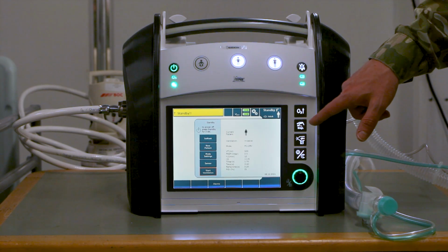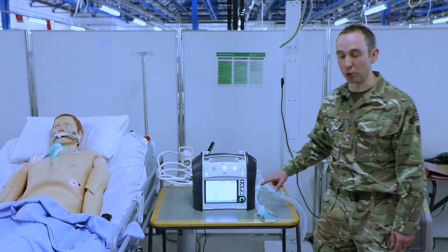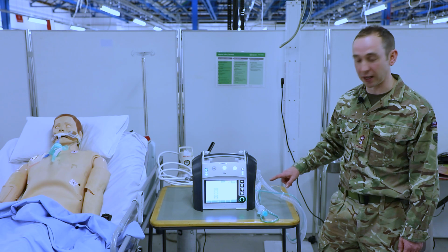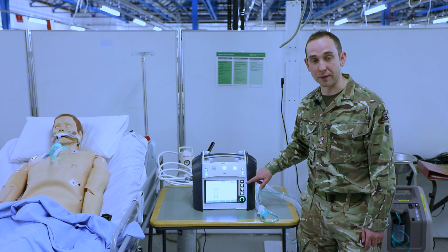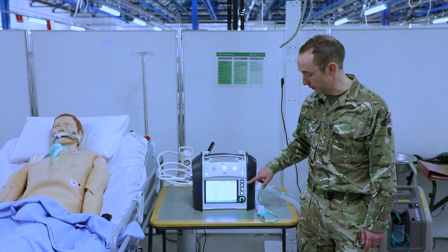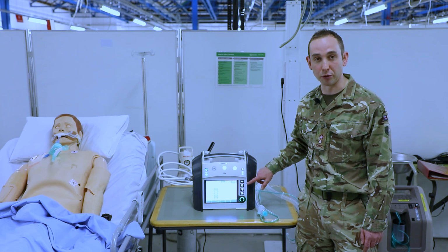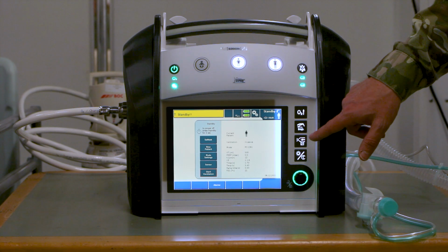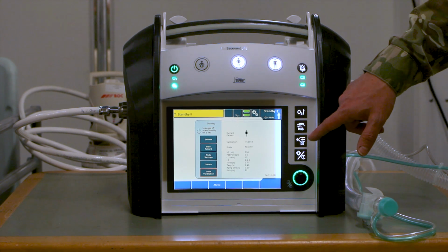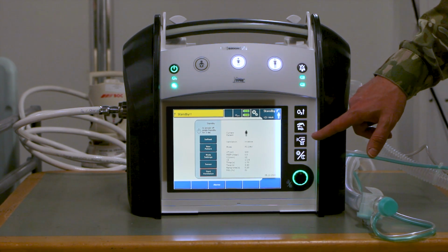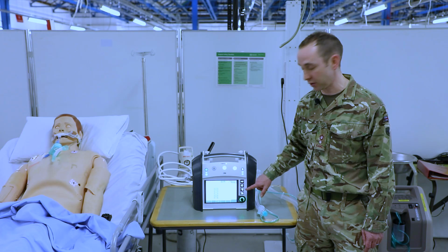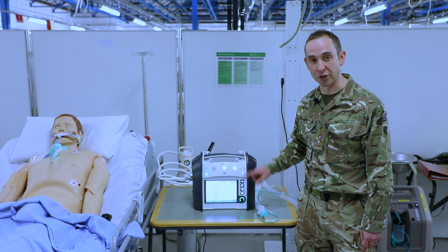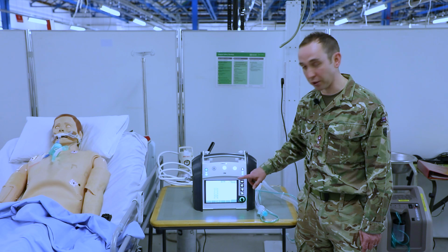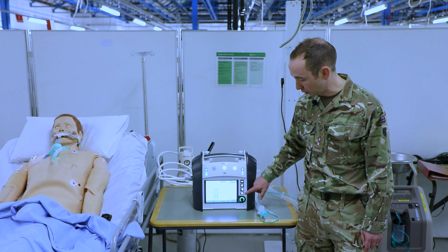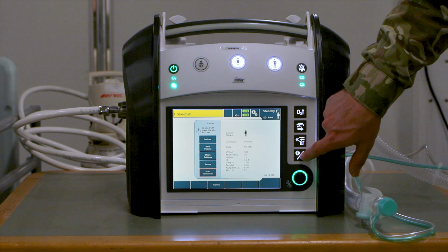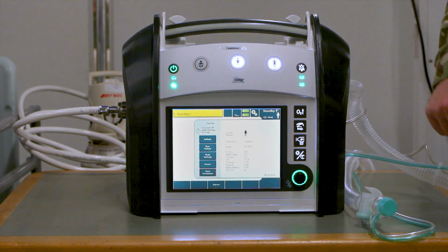The second button is an inspiratory hold. This can do an inspiratory hold at the end of inspiration for up to 15 seconds. When it's set in volume mode, this will do it at the peak pressure set. In pressure control, it'll do it at the P-insp. You can also do a nebulizer. This can be preset for its duration of between 5 and 30 minutes. Again, this will only work when attached to high pressure oxygen, and that can be done in the settings menu. The last one is a day-night mode, which will dim the screen when pressed.